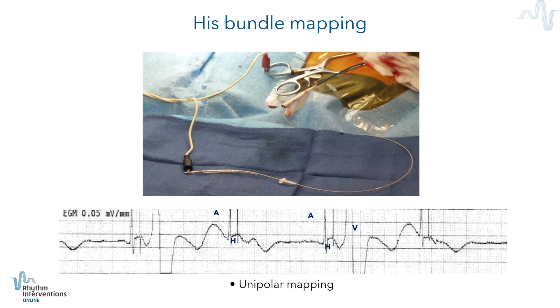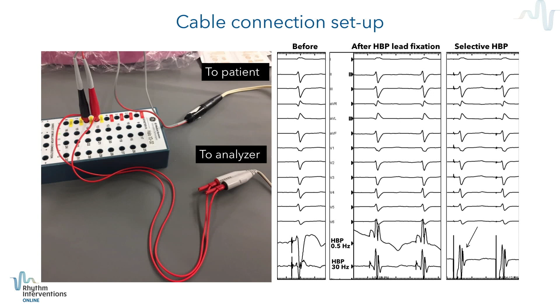And secondly, we also need to ensure that you can record injury current potentials in the His bundle. And as you can see in this example, the middle panel has a high-pass filter that's been changed to 0.5 hertz that allows demonstration of His bundle injury current after implantation of the lead at the His bundle location. And then finally, you demonstrate selective His bundle pacing in this case.